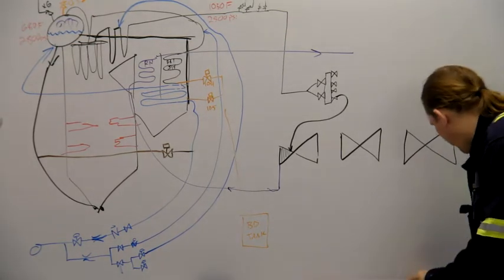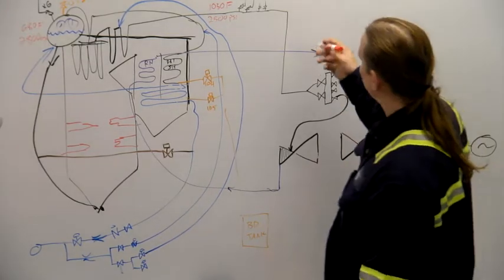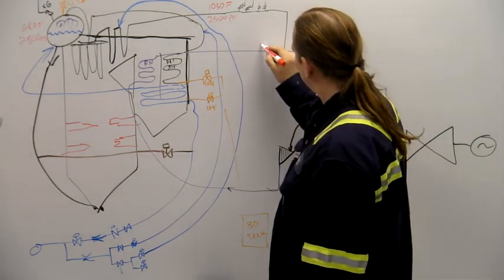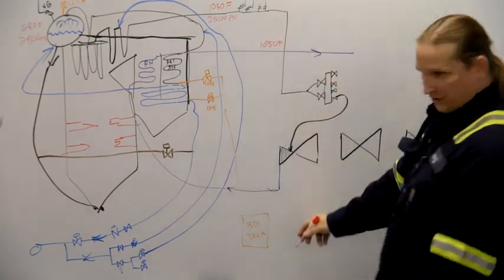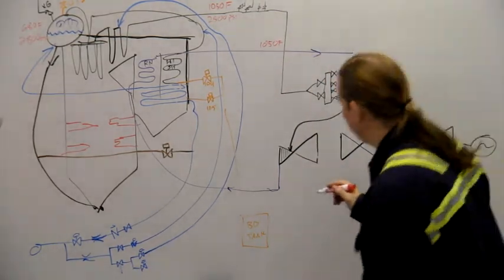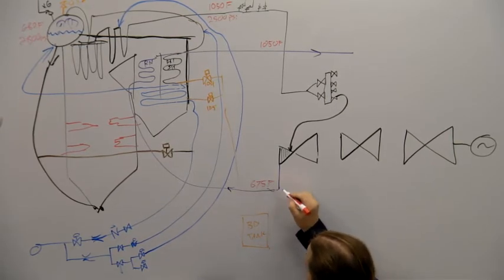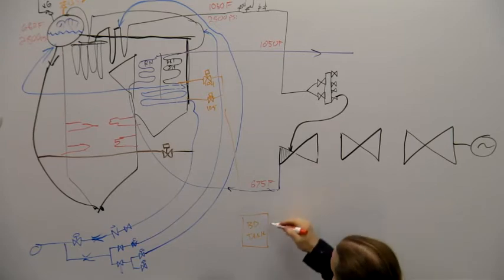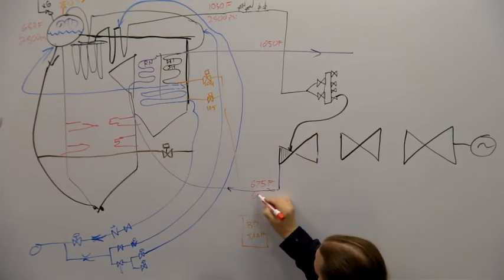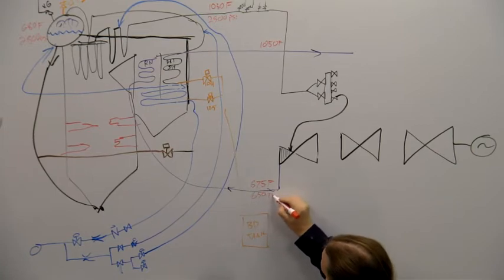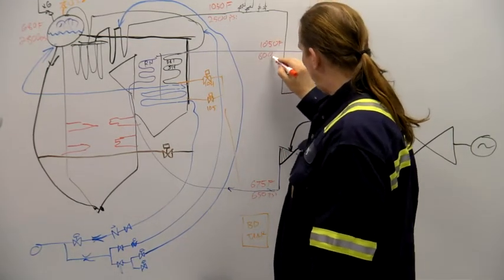How hot is hot reheat? 1050. Same temperature, 1050. How cold is cold reheat? 675, 680. Sure, 675, 680. I like those numbers. And then the pressure is like 650 on the cold and like 600 on the hot.